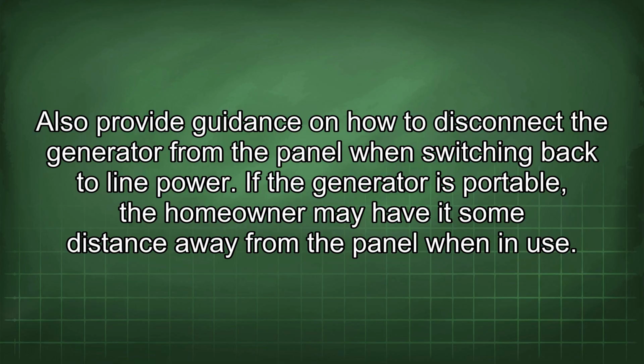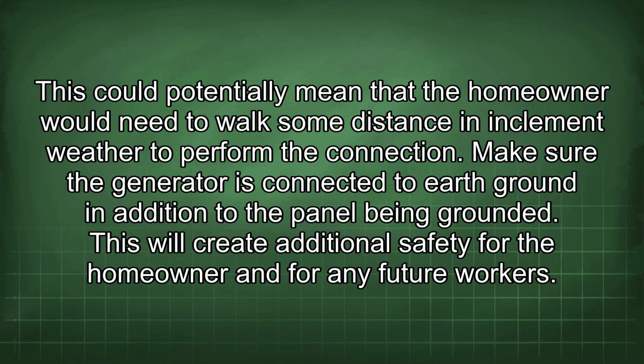If the generator is portable, the homeowner may have it some distance away from the panel when in use. This could potentially mean that the homeowner would need to walk some distance in inclement weather to perform the connection. Make sure the generator is connected to earth ground in addition to the panel being grounded. This will create additional safety for the homeowner and for any future workers.